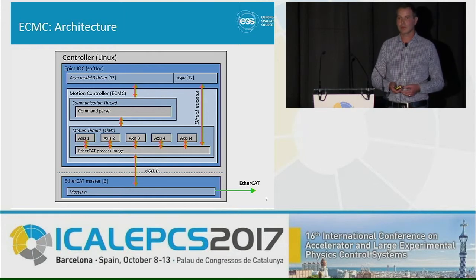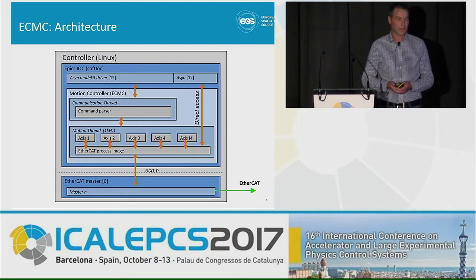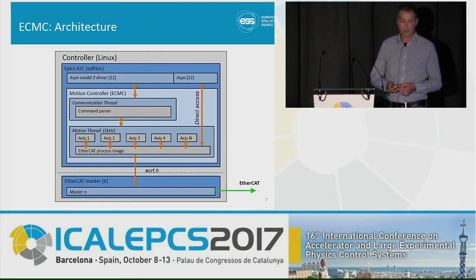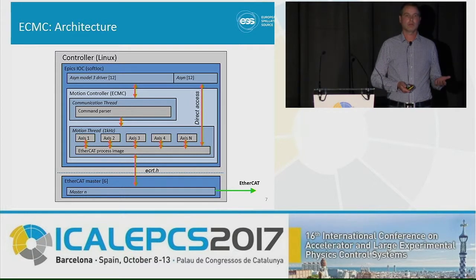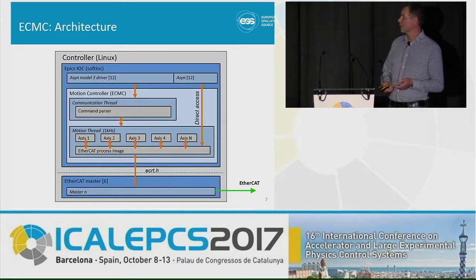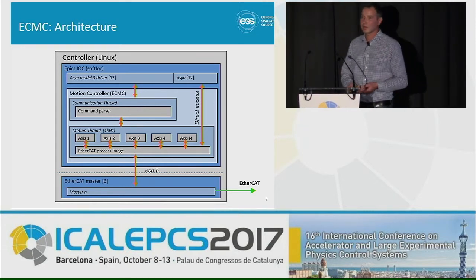Then we have a motion thread, which is the actual real-time thread. By default, we run this at one kilohertz, but it can also be other speeds. This thread is responsible for executing all motion algorithms, represented by the axis boxes in the picture. It's also responsible for updating all information to the EtherCAT image — set point and actual values — transferred to the slaves by the EtherCAT master. We have chosen to work with the open-source EtherCAT master from Etherlab IGH. We also have a direct access feature to access the complete EtherCAT process image directly from EPICS records in real-time over the asyn interface.